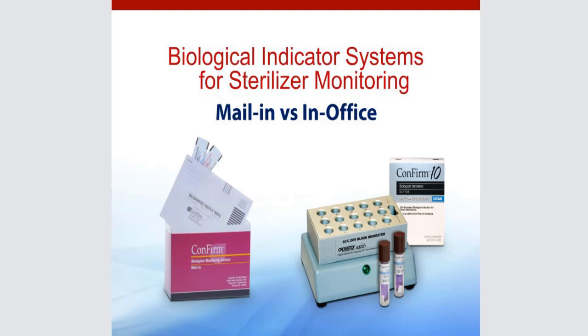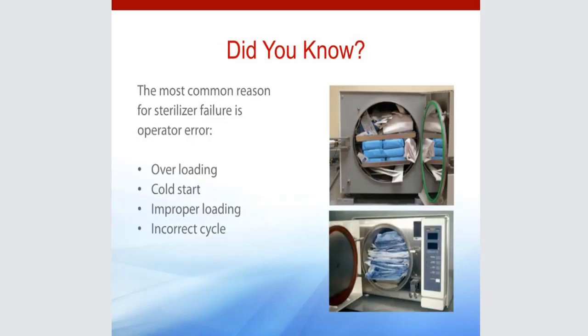Interesting thing, when people are doing the in-office testing, I've seen it where they have sterilized the self-contained vial and they take it out and they put it in the crusher unit to crush that ampule and release the fluid, and then I see them shake it. You do not want to shake after you have crushed the vial because that lid on the top is vented and you don't want to take a chance of cross-contamination from that filter paper that's on the lid. You can tap it vertically upside down if you need to get it to saturate the disc or the strip a little bit better, or you can flick the bottom with your finger. You just can't shake it. Not best practice.